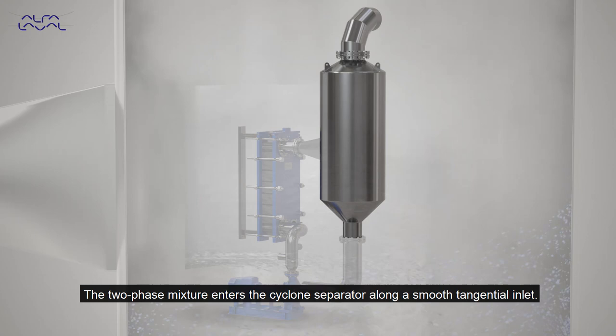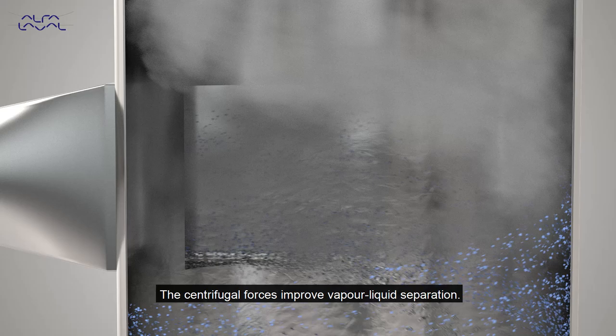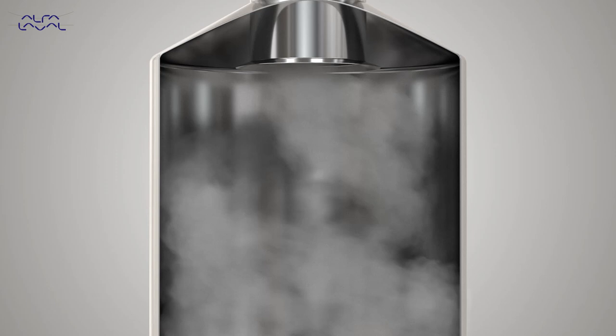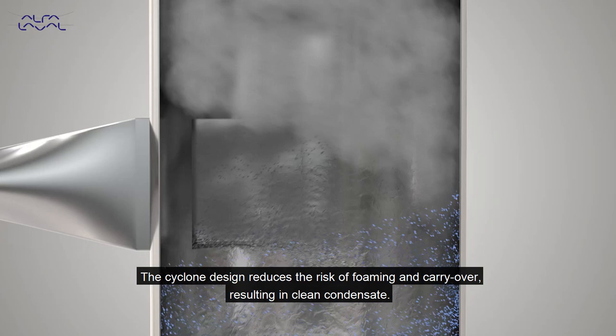The two phase mixture enters the cyclone separator along a smooth tangential inlet. The centrifugal forces improve vapour liquid separation. Low density steam rises from the circulating fluid into the space above where mists and fine droplets are removed. The cyclone design reduces the risk of foaming and carry over resulting in clean condensate.